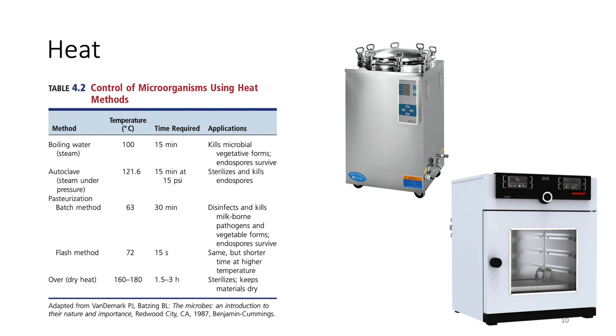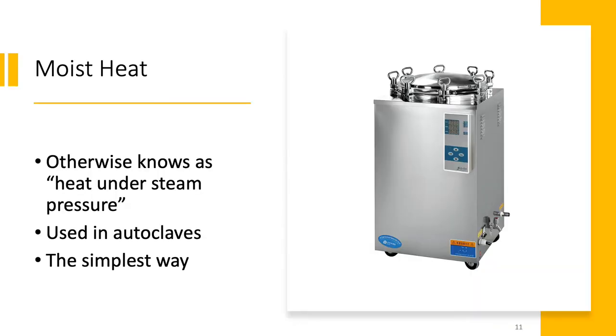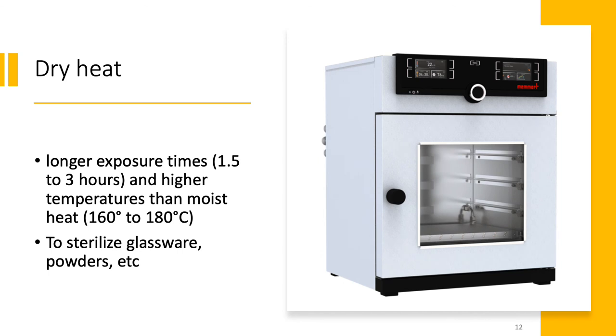This allows proper penetration of steam. The most common method of sterilization is using moist heat, otherwise known as steam under pressure, which is the principle used in autoclaves. This is also the simplest way to disinfect your objects. Dry heat requires longer exposure times of 1 to 3 hours, and is used to sterilize glassware and materials that cannot come in contact with water, such as powder.